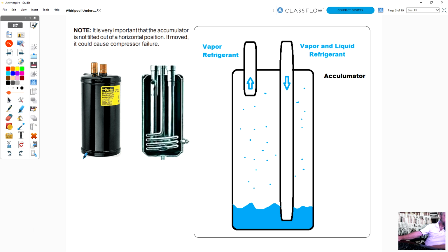So, accumulator, here's what an accumulator looks like. And this is one that's cut open. I did a little bit of a drawing to sort of explain. So what happens is they pump into the accumulator, and refrigerant is forced to the bottom of the accumulator. So refrigerant that's in liquid form is too heavy to go back out of our accumulator, so it'll be trapped at the bottom. But this is going back to our suction line of our compressor. So that suction line is going to take all this vapor and pull it back into the compressor, and that'll lower the pressure on our accumulator, causing the remaining liquid refrigerant to boil off as a vapor, so that we prevent it from going into the compressor as a liquid with an accumulator. That's the main purpose of that.